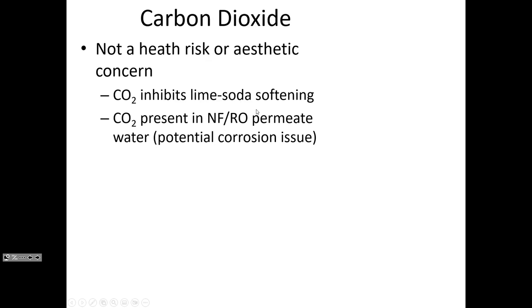Carbon dioxide is not a constituent that has direct health risks — it's mainly an issue of economics. If CO2 is dissolved in water, it can inhibit lime soda softening, meaning you'd have to add more lime than otherwise to increase the pH. In the lime soda softening process, we're trying to increase the pH so that calcium carbonate will precipitate out and be removed through filtration. CO2 keeps the pH abnormally low, so you have to add more lime than you otherwise would.